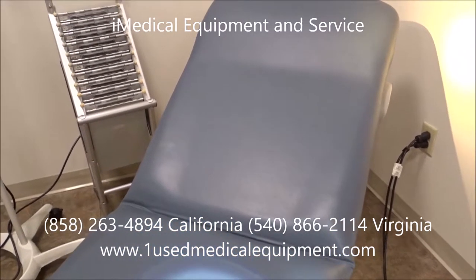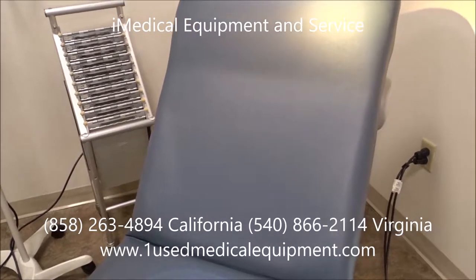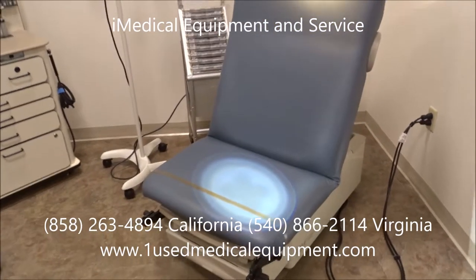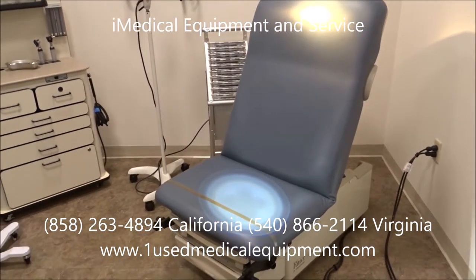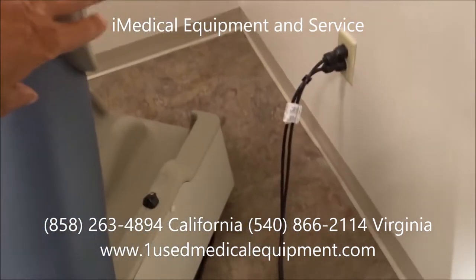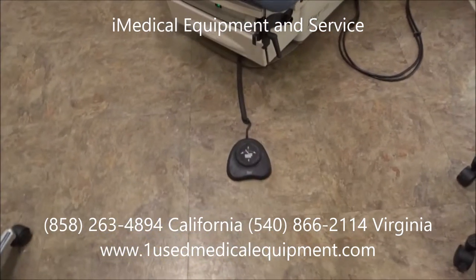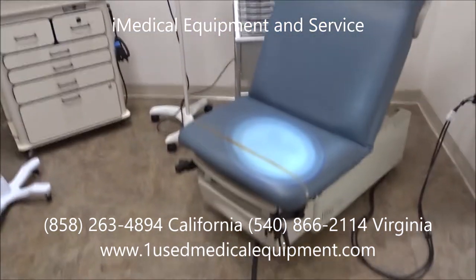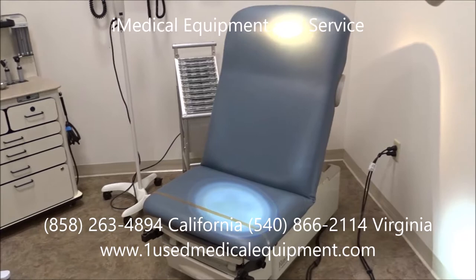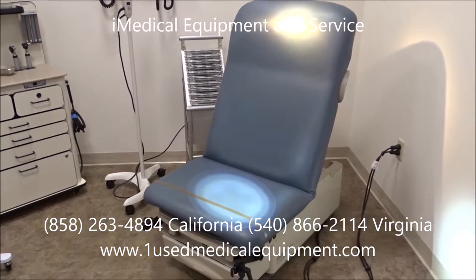So the Ritter 222 and the 223 are basically the exact same table. The only difference is that the Ritter 222 has an adjustable manual top. So to adjust the top on the 222, you would come over here and you could adjust the top. With the 223, you have that built in on the power foot switch.